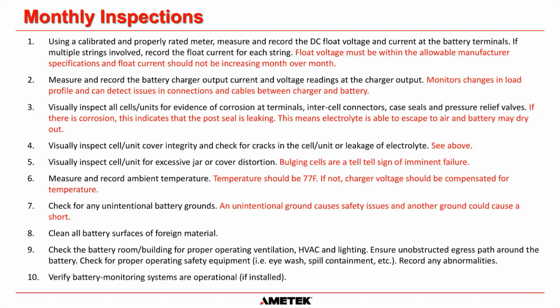You should also measure and record the battery charger output current and the voltage readings at the charger output. That's what IEEE recommends. And that monitors changes in the load profile and can detect issues in connections and cables between the charger and the battery. Because remember, in many circumstances, the charger is not going to be in the same room as the battery. So it could well be that there is an external battery disconnect between the charger and the battery. And if somebody accidentally left that open, or if the contacts in that battery disconnect aren't working very well, you could, in theory, measure 135 volts at the output of the charger.